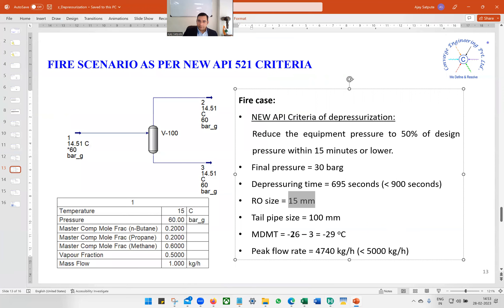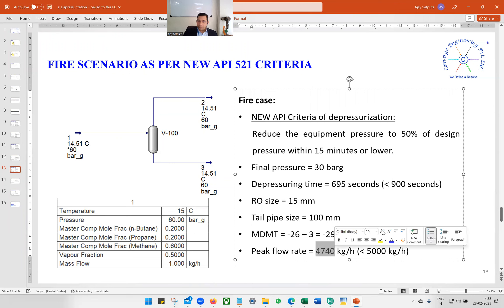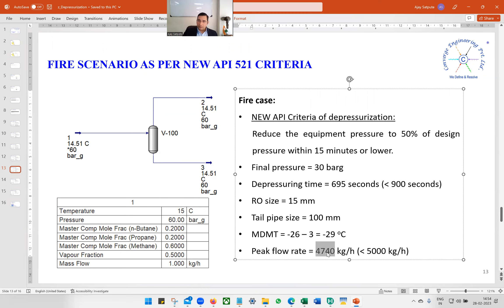The MDMT is minus 26 minus 3, giving minus 29°C, and the peak flow rate is 4740 kg/hr. This is good news — the existing flare header cannot handle more than 5000 kg/hr, and we are now below that limit. So the depressuring time of 695 seconds is within 900 seconds, and the peak flow of 4740 kg/hr is less than 5000. This proposal will be acceptable to the client.